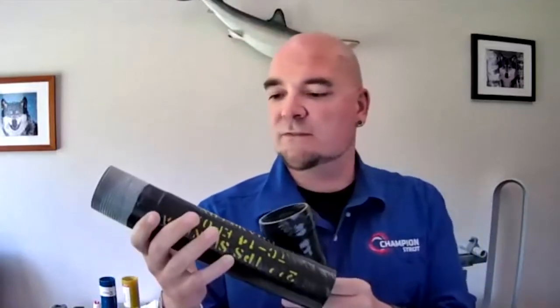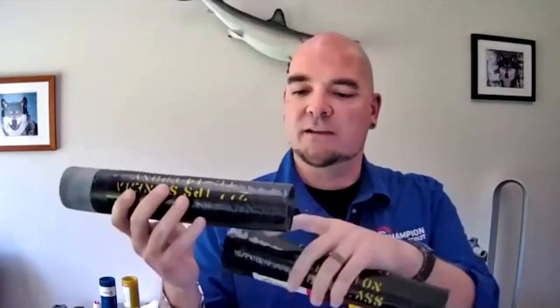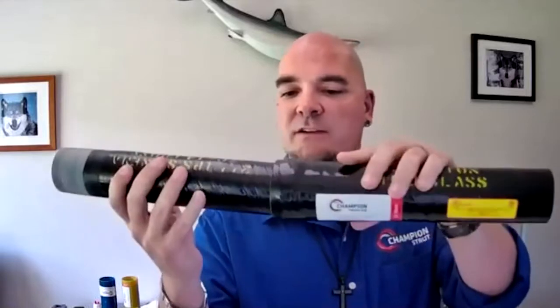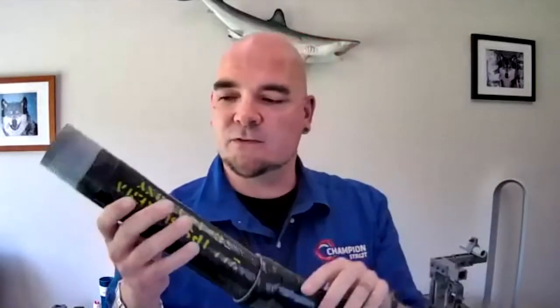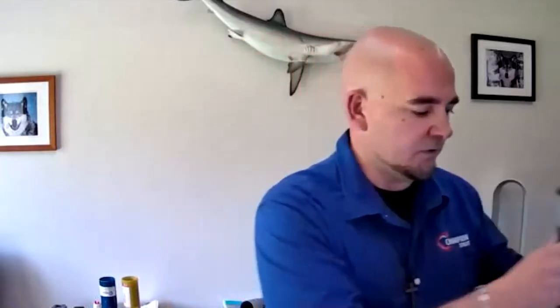If in the event you have to make a field cut, you'll sand down this area, apply the straight end, and you still have 500 pound pull out even without the interference joint ridges.